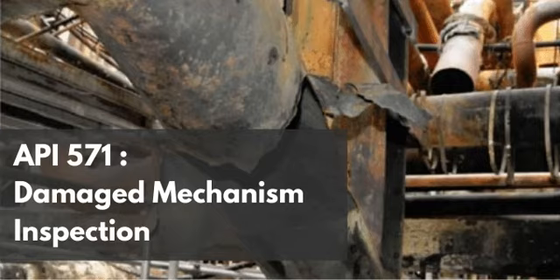And what about cracks that are deeper in? Right, for probing deep into the volume of a thick weld to find subsurface intergranular cracking, advanced ultrasonic methods like shear wave or phased array ultrasonic testing are deployed. They basically bounce high-frequency sound waves through the steel and look for the ultrasonic reflections that bounce back off the crack faces.